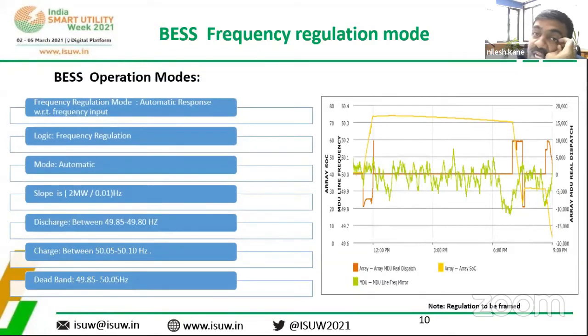This is the automatic frequency regulation mode in which we are operating, and this graph shows that with a slope of 2 megawatt per 0.01 hertz, we quickly charge and discharge within the appropriate limit of 49.85 to 50.05. These are the limits, and these are some pictures showing how the battery operated automatically.